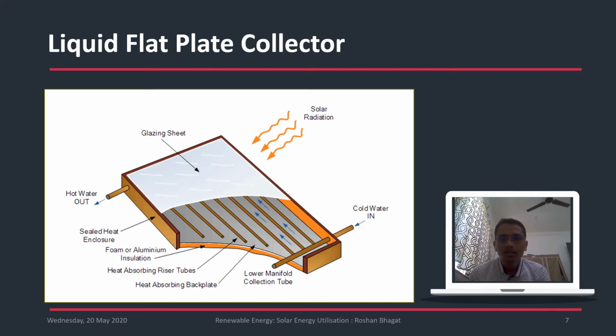One thing has to be remembered: the water which is supplied in this case should be free from salts and other foreign particles. What will happen if there are salts and sediments? They will deposit on the inside surface and that will prevent the flow of heat, and the heat will not be effectively utilized. So this is one thing that has to be understood.